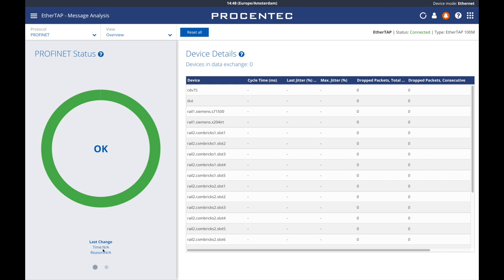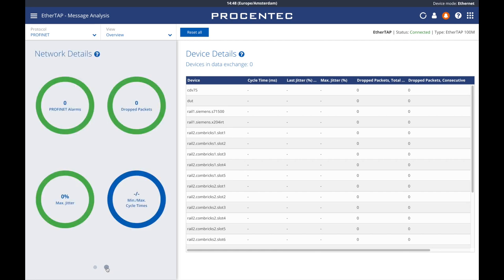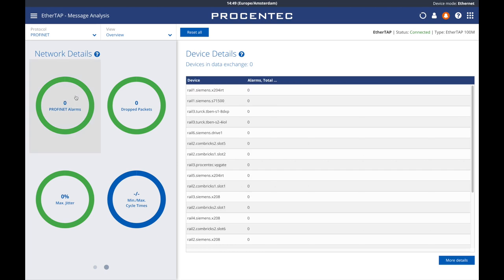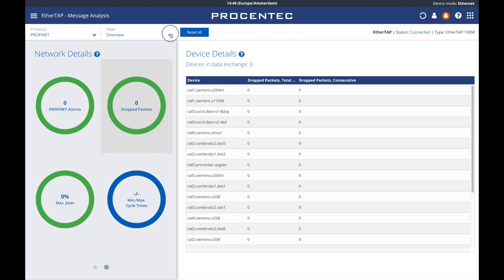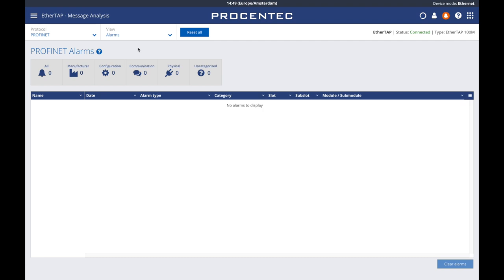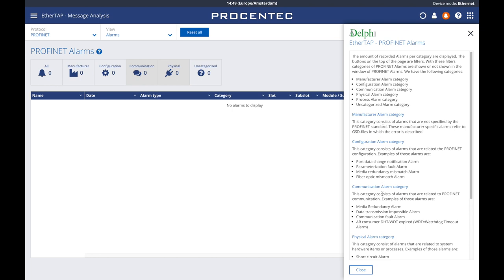Below, it indicates the last time there was a change in status and reason. These network details can be seen by switching the view down here — you see the number of alarms and dropped packets, percentage of jitter, and the minimum and maximum cycle times. The device details chart on the right is a list of devices with all relevant passive information for each. If you click on a specific network detail on the left, it will filter the information in the chart, only showing the specific information. From the view drop-down menu on the upper bar, it's possible to switch to alarms and message recording. Let's click on alarms. Here you are given a detailed list of all the alarms registered from the device — the device name, timestamp, type of alarm, and category. It's also possible to filter those alarms by selecting the type at the top. By clicking on Delphi, you can see the criteria for each category.